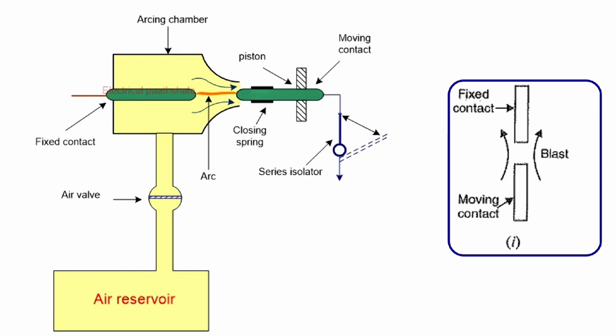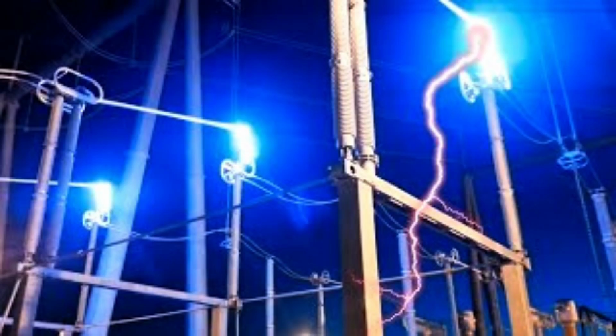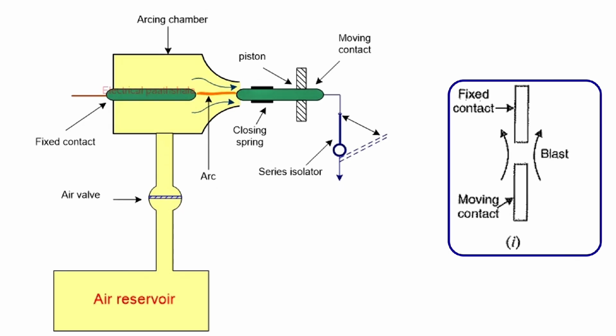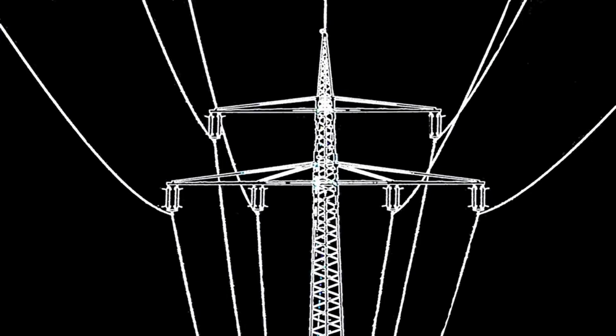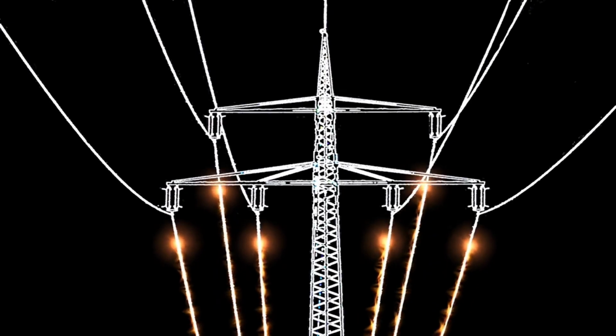The axial blast type offers several benefits, including fast arc extinction. By directing the compressed air along the arc path, the axial blast helps to cool and extinguish the arc quickly, which reduces the risk of damage to the circuit breaker and other equipment. Fast arc extinction is critical in high-voltage transmission systems, as it helps to minimize the duration of faults and prevent damage to equipment. Furthermore, the axial blast type helps to increase the dielectric strength of the gap between the contacts. By blowing compressed air along the arc path, the axial blast helps to remove ionized particles and increase the dielectric strength of the gap. This reduces the risk of reignition and ensures reliable operation of the circuit breaker. So, this is how the axial type of air blast circuit breaker works.